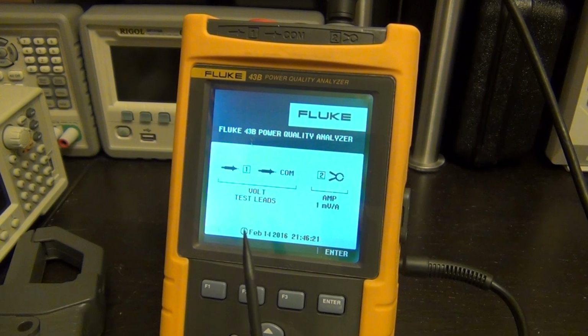But the main front screen right now is showing us what the instrument is expecting in order to be able to do power quality analysis. On channel 1, input 1 is expecting us to give it the voltage, and on channel 2 it's expecting a current probe with a sensitivity of 1 millivolt per amp. And that can be changed, of course, in the configuration, but this is how it's configured right now.